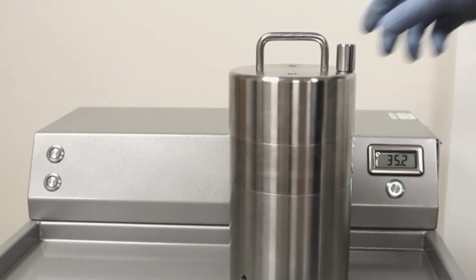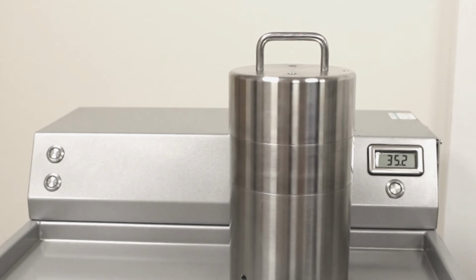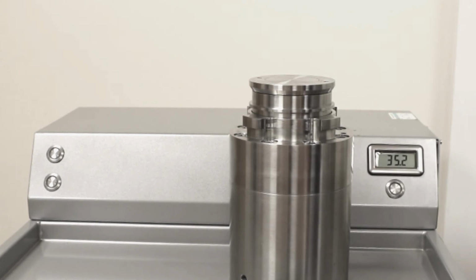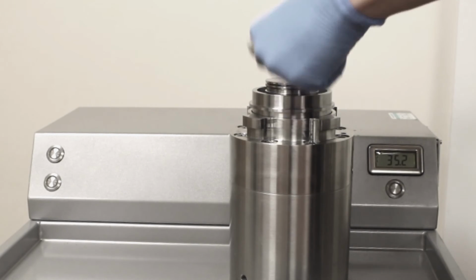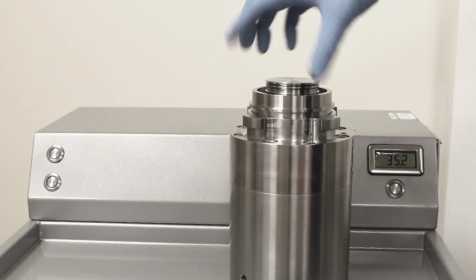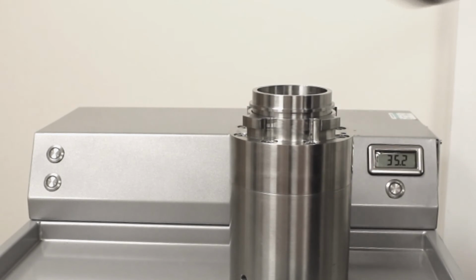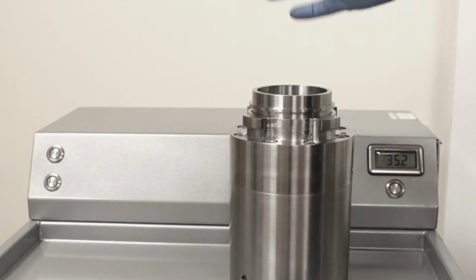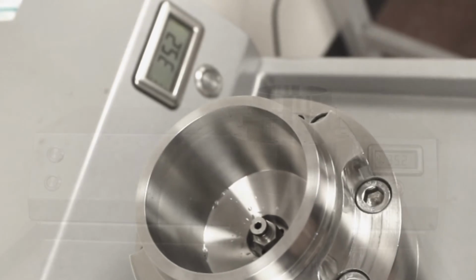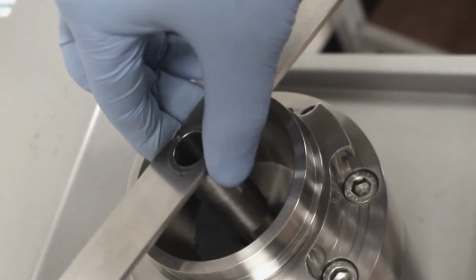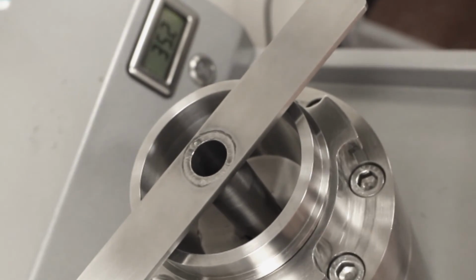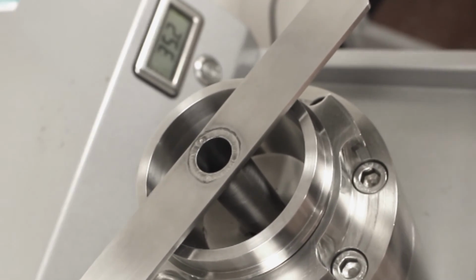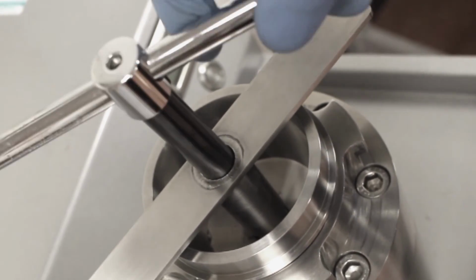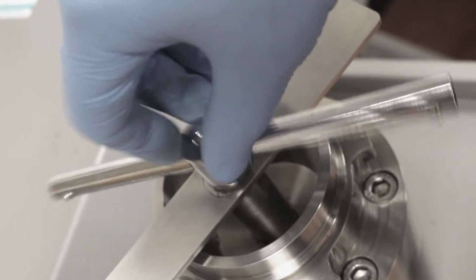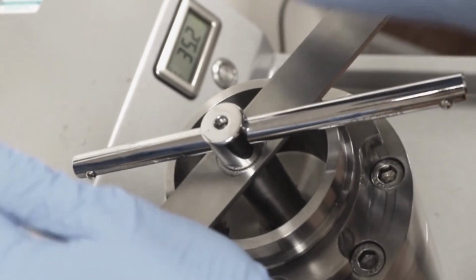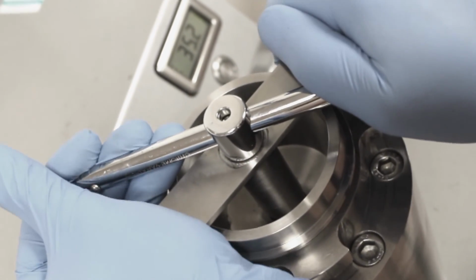To change the jet, remove the operator probe, the main lid, the outer cup lid, the inner cup assembly and the anti-foam pin. Locate the square drive T-bar into the outer cup, the long 11mm and T-bar onto the jet retainer and squeeze the two together.